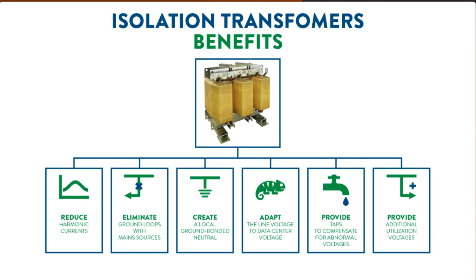The installation of isolation transformers is closely related to the installation of UPS systems. They are meant to isolate the UPS system from the mains or to isolate the loads from the UPS system itself. These UPS systems come in different configurations based on the layouts of the data center itself. This can be single mains without bypass layout, where the mains that come from the grid are considered particularly unreliable, and therefore the loads cannot be supplied directly from the grid.